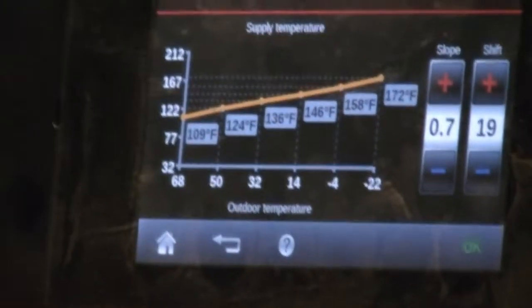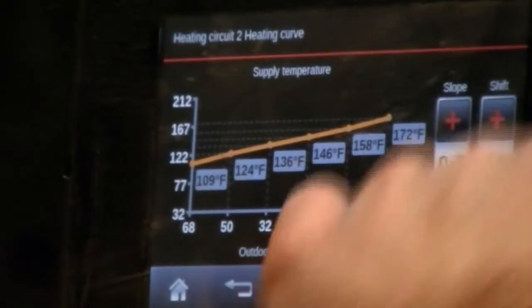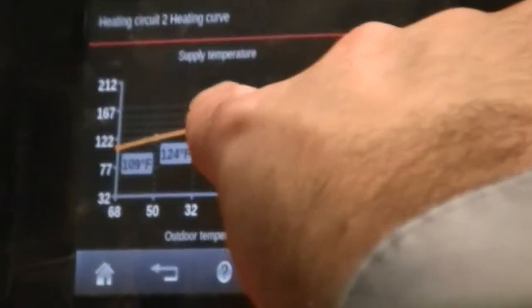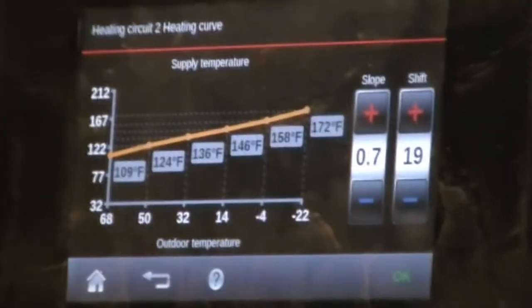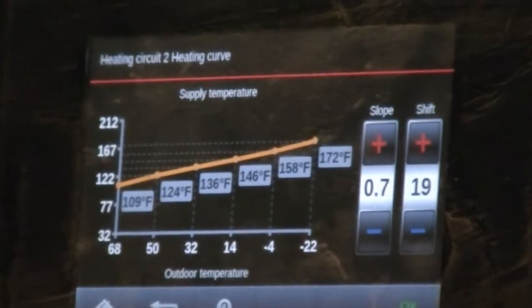So now, this heating curve is your heating curve chart. So on the bottom row, you'll see your outdoor temperature. On the side row here, the left-hand row, you'll see your boiler water temperature, and this is the curve that you pick. So now, the way we're set up now, you'll see that at about 14-degree outdoor temperature, the boiler is going to run at about 140 degrees. Okay? If you find that that's not where you want it to be, you want it warmer or colder, you can actually adjust these two numbers.